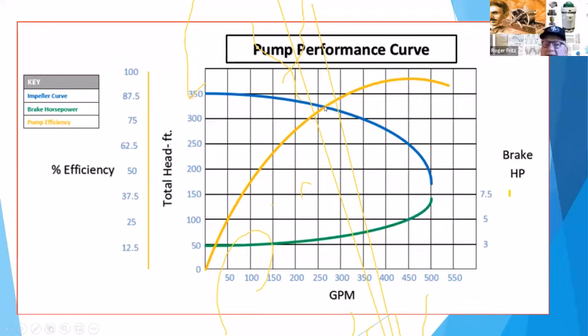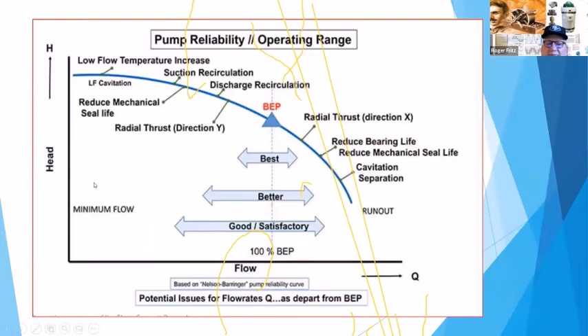So we get the highest percentage of efficiency of the pump curve running on the motor, and the motor is running within tolerance. So the issue is the design point of the pump itself originally, and the design point of the motor itself. So I highly recommend this, because these efficiencies can fall way off the curve, by the extra effect that happens as it falls in and out of its optimal point.